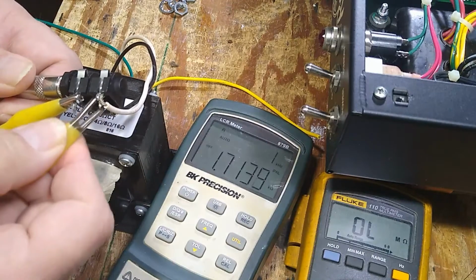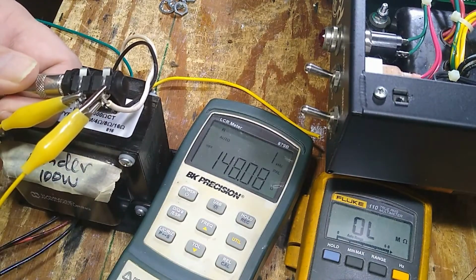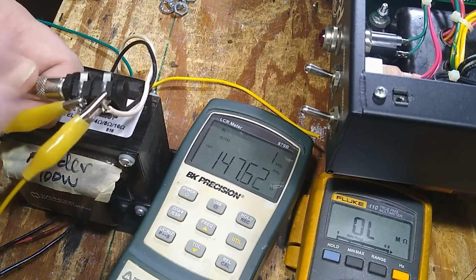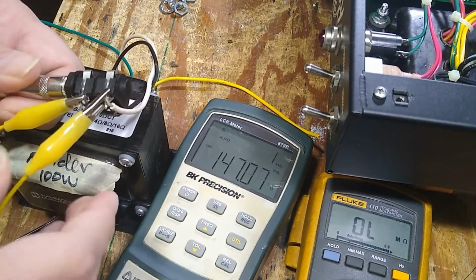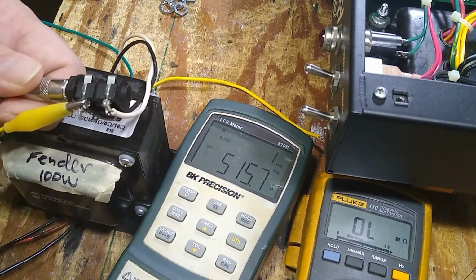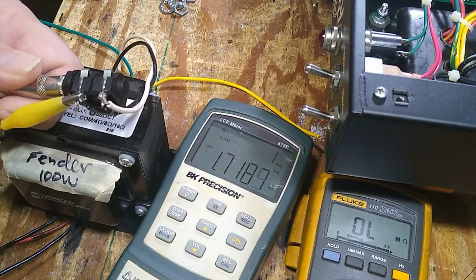Now that's an example of reflective resistance. The short on the secondary is being reflected back to the primary. You can't measure that using a multimeter. You've got to use an LCR meter.